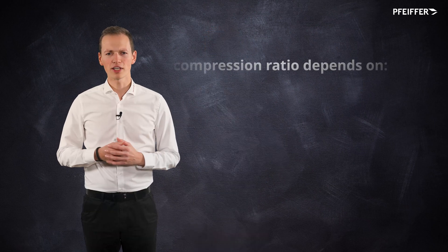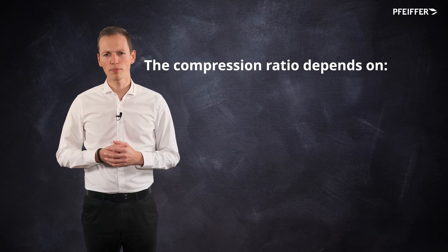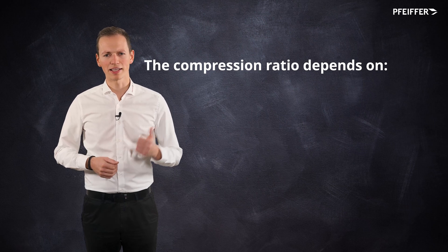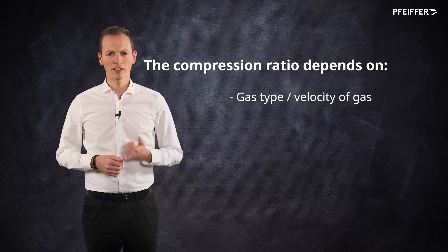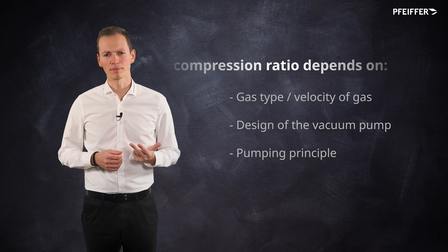The compression ratio depends on several factors. The most important ones are the gas type, the design of the pump, and the pumping principle.